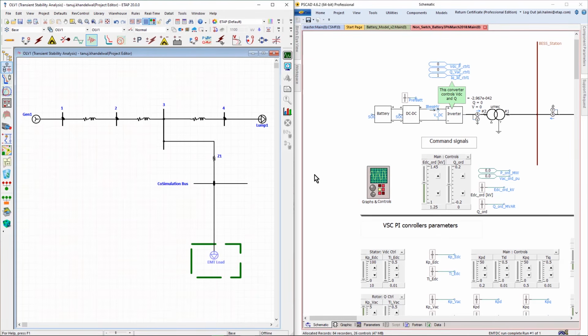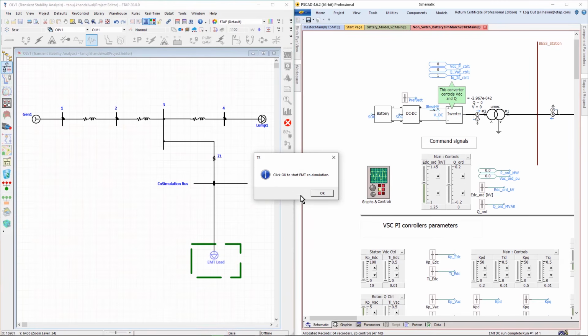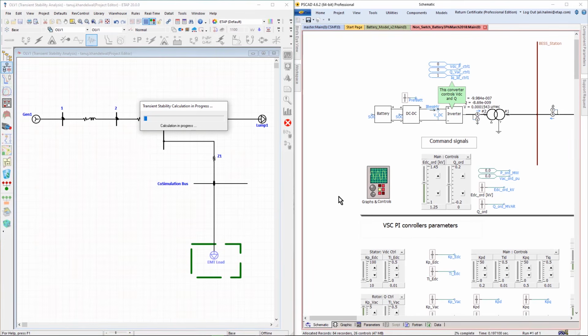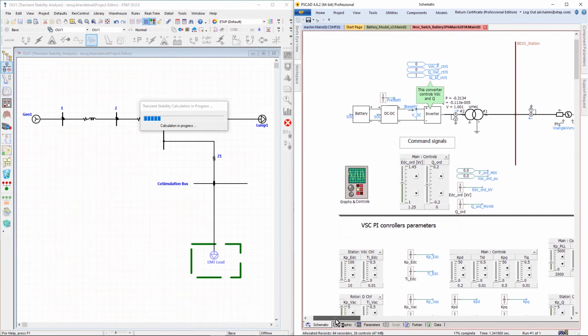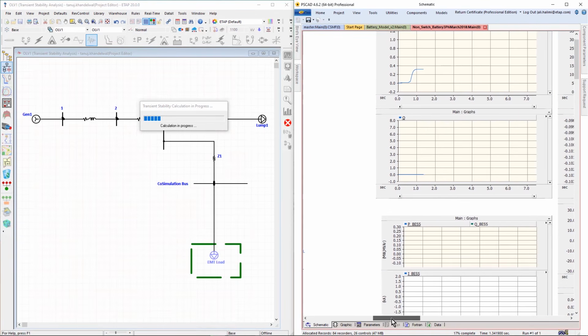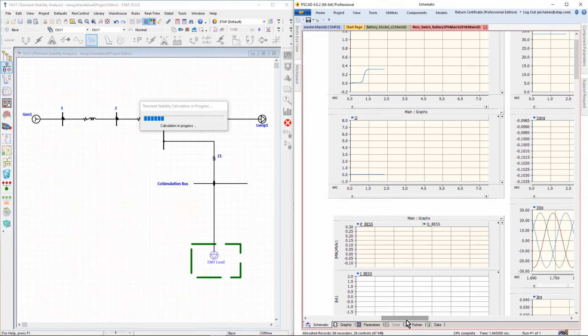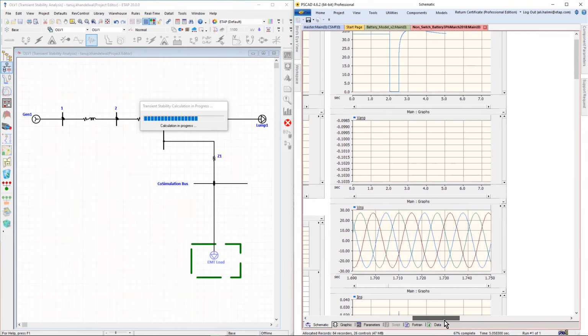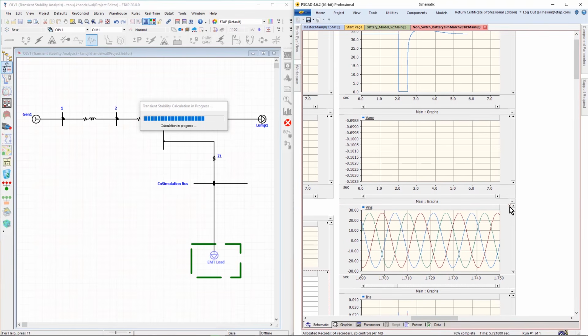When the co-simulation process is begun, you can just simply run ETAP transient stability, and when ETAP is essentially connected to PSCAD, you can go ahead and click OK and allow ETAP to run the transient stability calculations while PSCAD is running its EMT-based simulations. You can also observe on both sides what is the calculation or the simulation response from the combined or co-simulated approach. And in this case, you can observe what the ETAP interaction is with the PSCAD along with the PSCAD EMT time domain simulations as well.